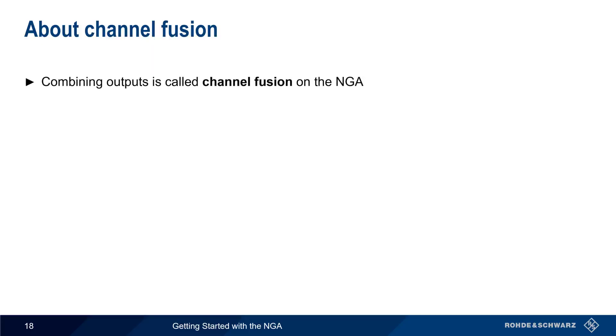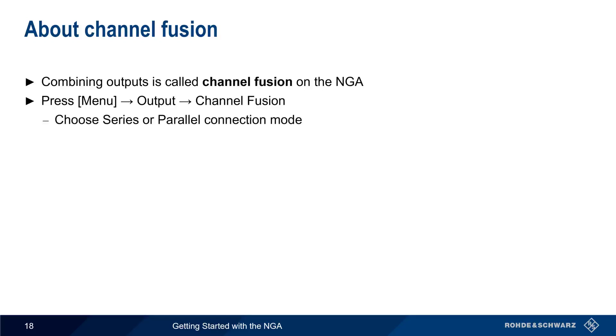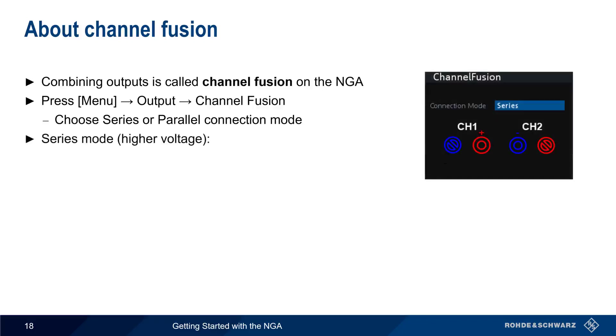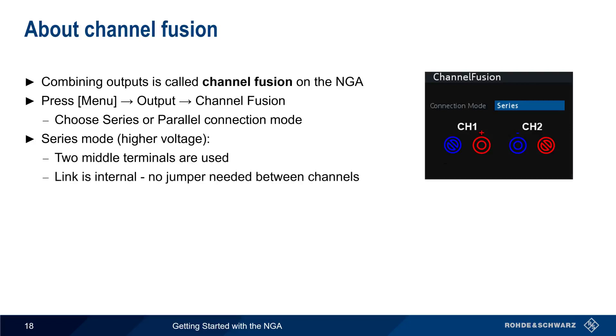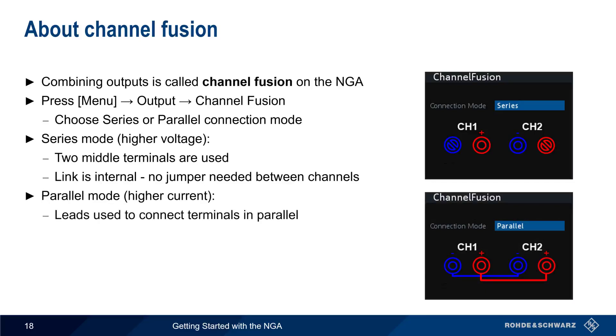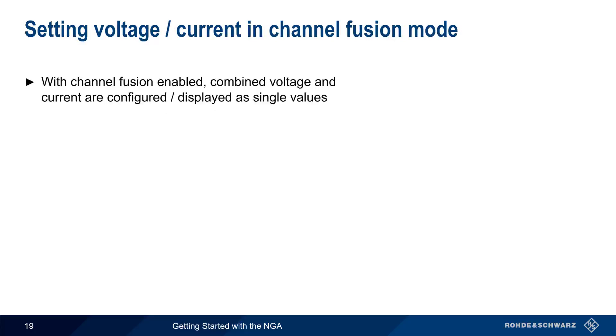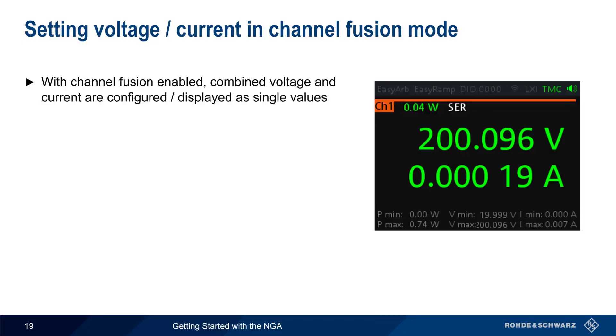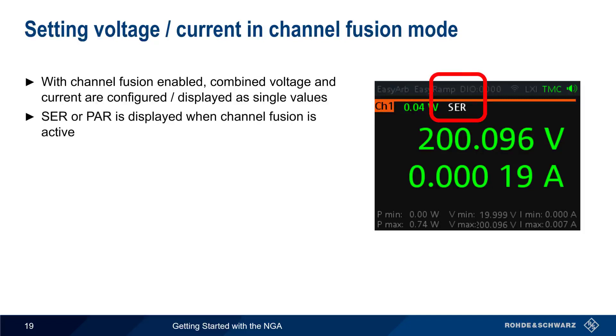On the NGA, combining outputs is called channel fusion. Channel fusion is enabled by pressing the menu hard key, then selecting output channel fusion. The two modes of channel fusion are series and parallel. In series mode, which is used to produce higher voltages, the two middle terminals are used for the combined voltage output. The link between these channels is made internally, so no jumper between the channels is necessary. When using parallel mode to produce higher current, the leads must be manually connected to the terminals in parallel. Once channel fusion is enabled, the combined voltage and current is displayed and configured as single values on the NGA. In this example, two channels have been combined in series to increase the maximum output voltage to 200 volts, and series is now displayed to show that channel fusion is active.